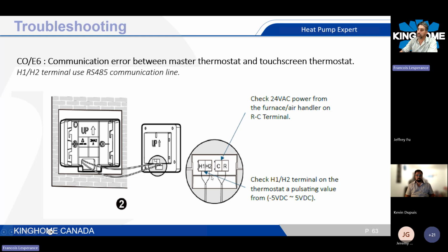Those terminals, you will see H1, H2, and your common and power from your 24 volt transformer. So now you can check directly on those terminals right here if you do have a pulsating value of -5 to +5. This is the easiest way to find it out. Or you can disconnect the wire and check on the wire directly if you have that pulsating value.